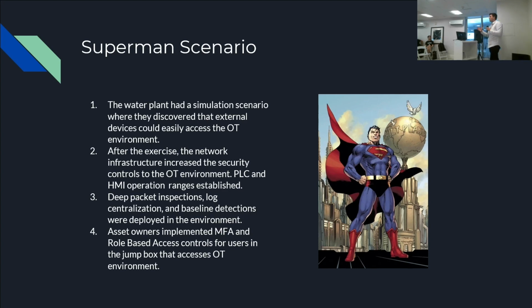Also, as was mentioned before, the operator realized what happened and quickly modified the parameters that were changed, thankfully. But we shouldn't have to rely on an alert or an operator. So in a good operational technology environment design, the controllers and the HMI would have had safety ranges established in order to avoid human disruption from modifying the values to dangerous values or creating unsafe conditions.